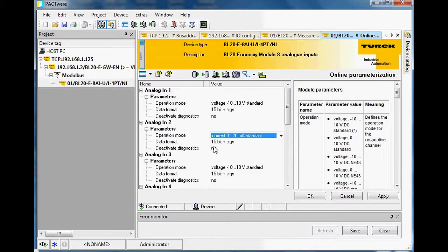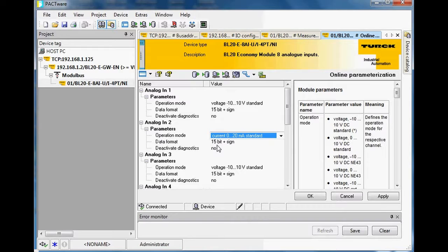I'm going to leave this one set to 0–20 milliamps. I also want to point out that the data format is 15-bit, so it's going to go from 0 to 32,767 over the span of that 0 to 20 milliamp value.